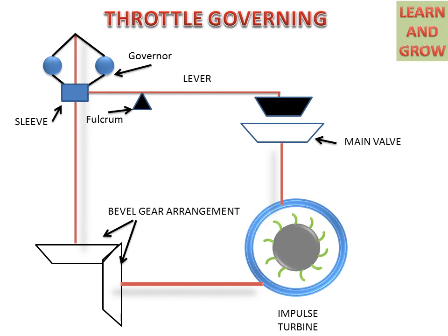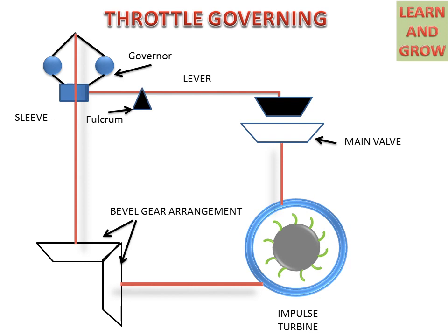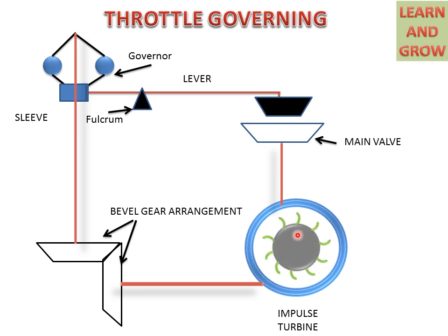Now we see the working of the Throttle Governing process and how it will work for maintaining the flow of water. When water comes from the main valve and strikes on the buckets of the impulse turbine, the turbine starts rotating. If the load is less, the rotor will gain high speed. For maintaining the flow of water coming from the main valve, this gear arrangement will work.